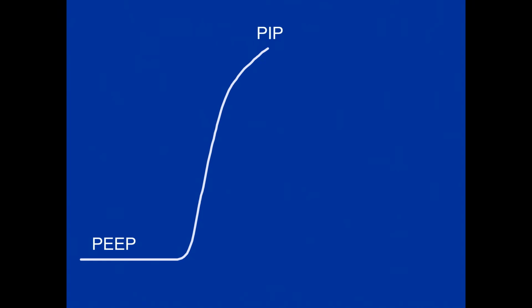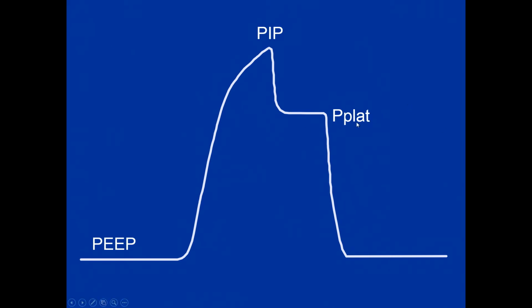This picture shows a pressure time scalar. PEEP would be considered your baseline, and the PIP, or peak inspiratory pressure, is the pressure that it takes to overcome the resistance to flow, not only in the patient's lungs, but also the resistance within the ventilator circuit and endotracheal tube. If we were to put in an inspiratory pause, this would stop the flow, which you can see at this plateau level, and it will in fact create an inspiratory pause and create what we call a plateau pressure. This plateau pressure is felt to be equivalent to end inspiratory alveolar pressure.